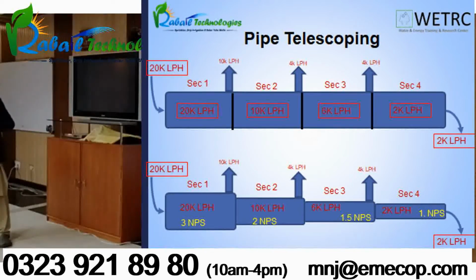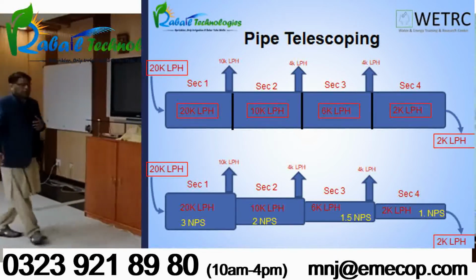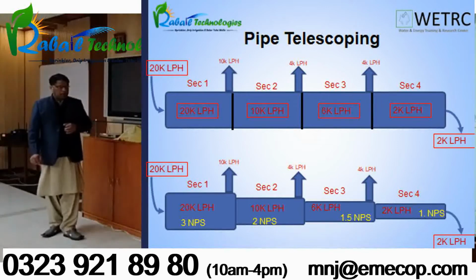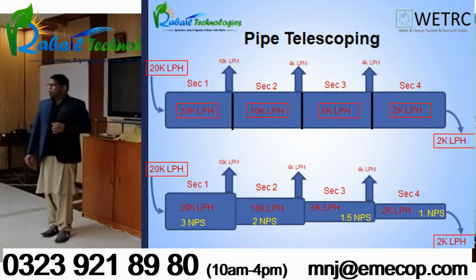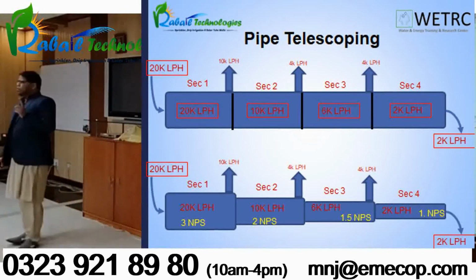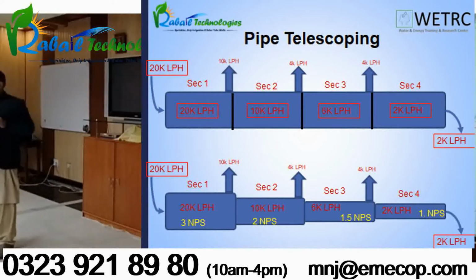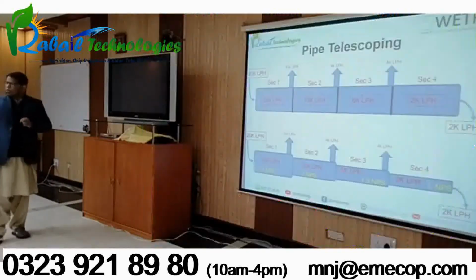Now in section 3, the flow rate is 6,000 liter. So again with that formula, I will determine what diameter is minimally required. For 6,000 liter, the requirement might be 1.4 inches, but as 1.4 is not available in the market, we have to go for 1.5. In section 2, the flow is 10,000 liter per hour. So again, with the help of that formula, we will get 2 inch, and then with 20,000 liter, we will get 3 inch pipe.